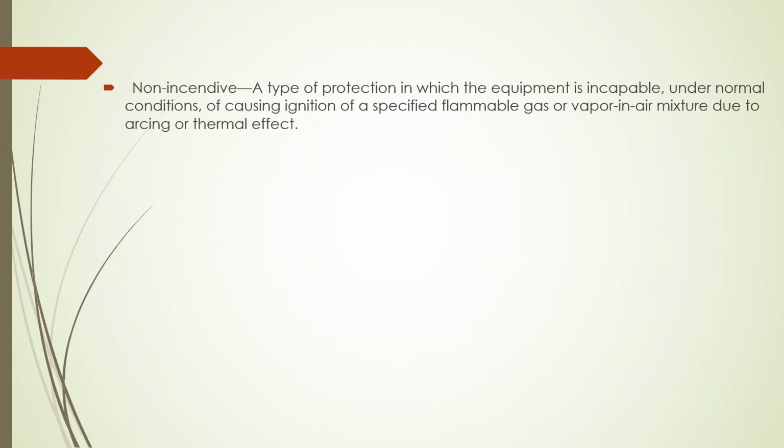Non-incendive, a type of protection in which equipment is incapable under normal condition of causing ignition of a specified flammable gas or vapor in air mixture due to arcing or thermal effect.